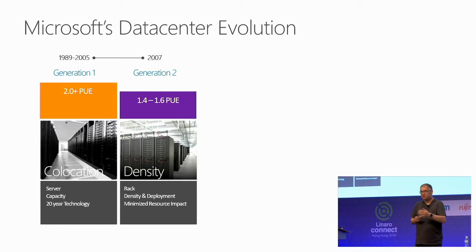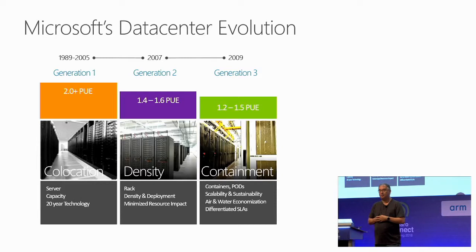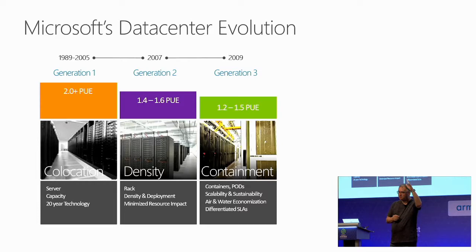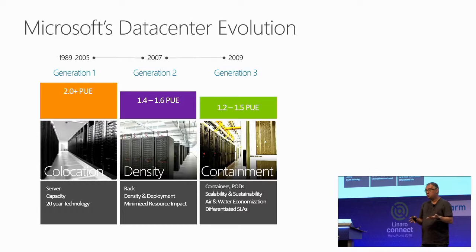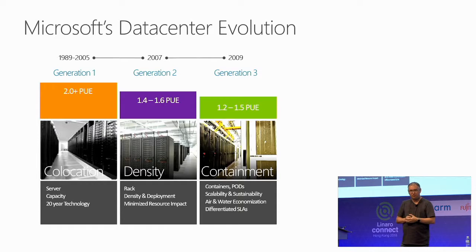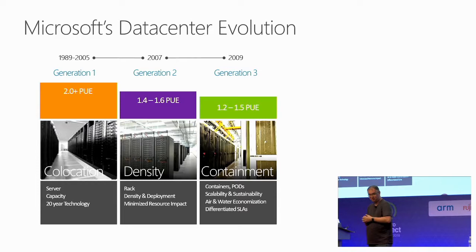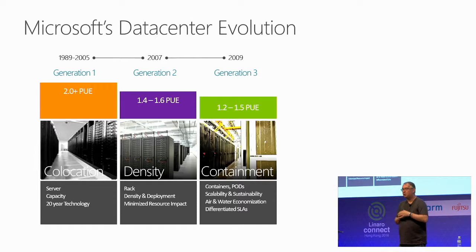The second generation was very much focused on density — how do we pack as much as we can? The third generation is actually where we introduced zones, with cold aisles and hot aisles. Cold air comes in, you suck it through the nodes, and exhaust it out through the hot aisle. We actually have all the I/O on the front end of the machine so that operators are in the cold aisle while working, because those hot aisles can get pretty hot indeed. That clearly improved efficiency a lot — we went to 1.2 and 1.5 PUE.